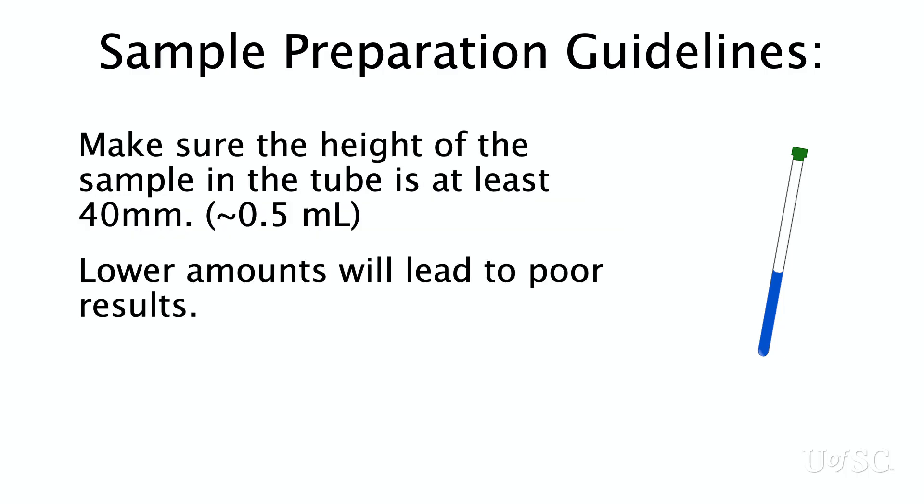Make sure your sample height is at least 40mm. This is about the width of your first three fingers. Shorter samples will be difficult to shim and lead to poor results.